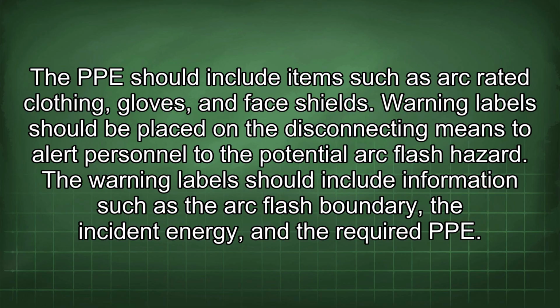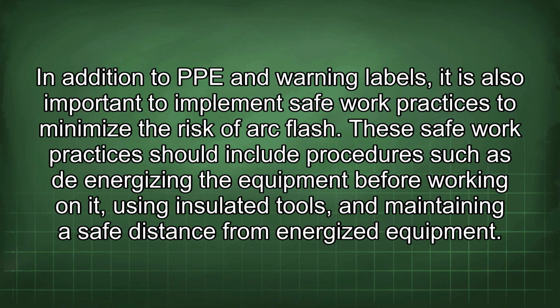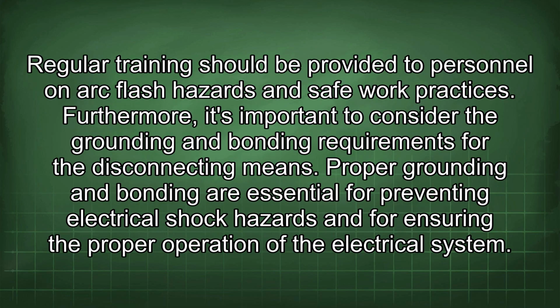The PPE should include items such as arc-rated clothing, gloves, and face shields. Warning labels should be placed on the disconnecting means to alert personnel to the potential arc flash hazard. The warning label should include information such as the arc flash boundary, the incident energy, and the required PPE. In addition to PPE and warning labels, it is also important to implement safe work practices to minimize the risk of arc flash. These safe work practices should include procedures such as de-energizing the equipment before working on it, using insulated tools, and maintaining a safe distance from energized equipment. Regular training should be provided to personnel on arc flash hazards and safe work practices.